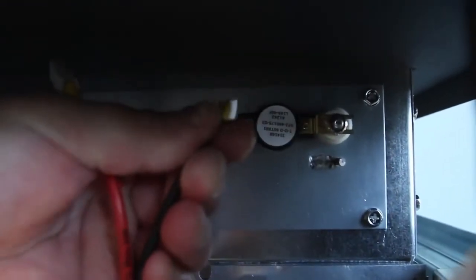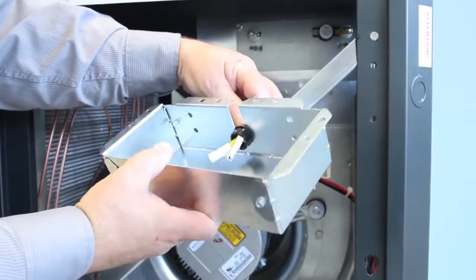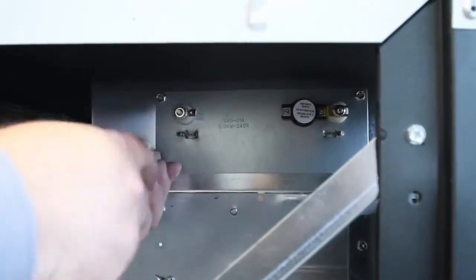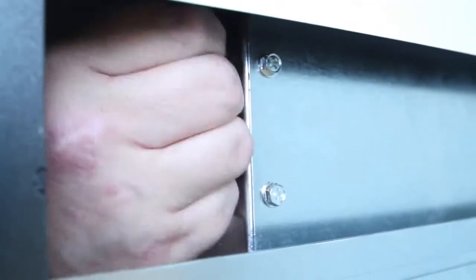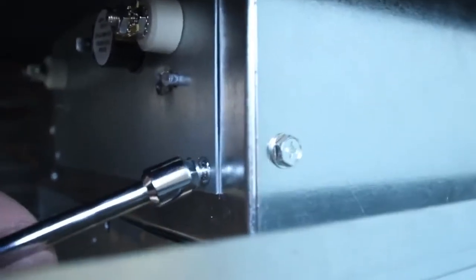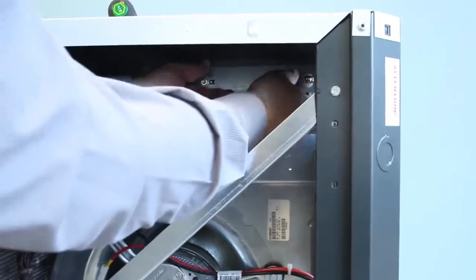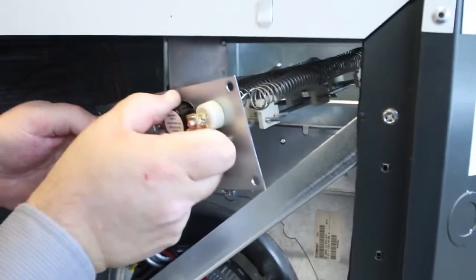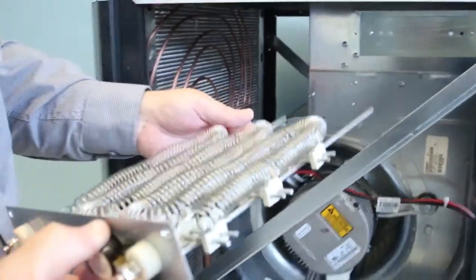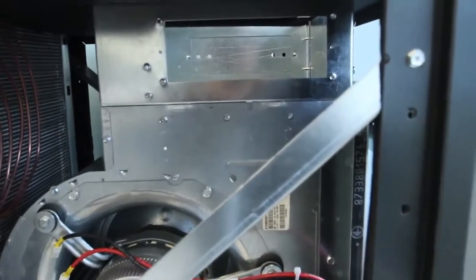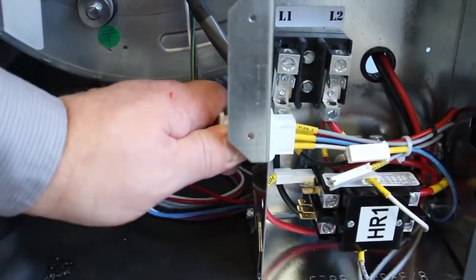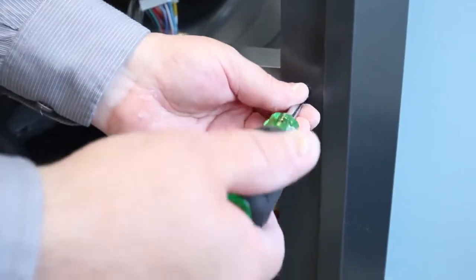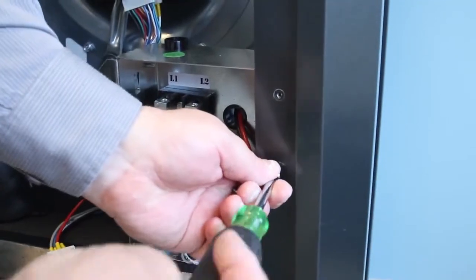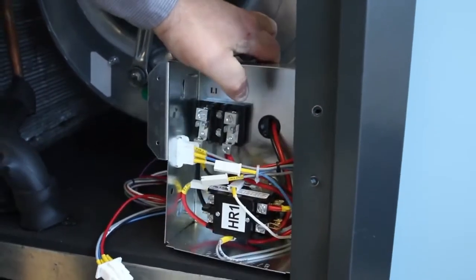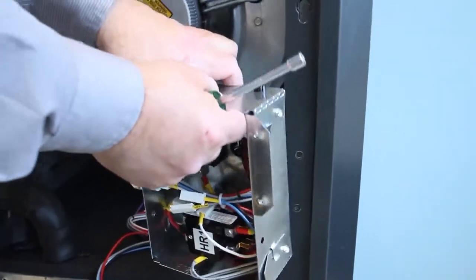Next, disconnect the high voltage wiring at the electric heat elements. Once the wires are removed, remove and retain the electric heat elements from the blower collar. Once the elements are removed, disconnect the main electrical e-box plug that is located just outside of the heater e-box in the blower compartment. Once that plug is disconnected, remove and retain the electric heat e-box by removing the 2 screws in the side of the box.